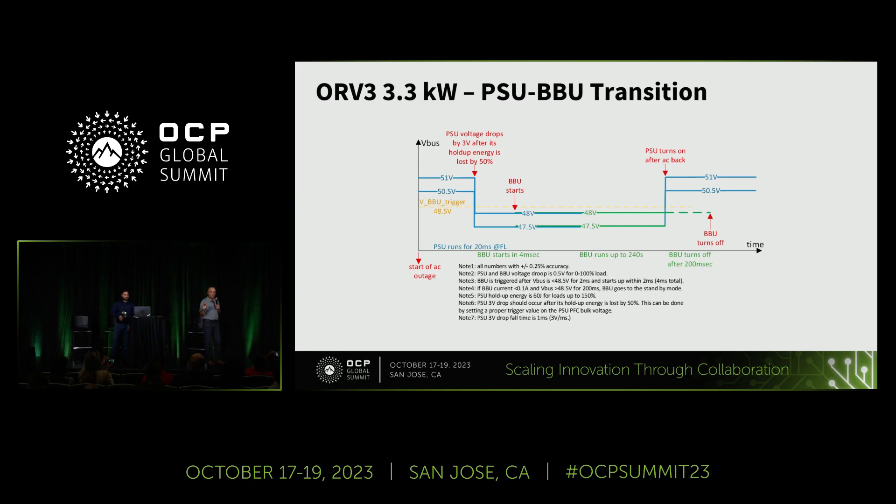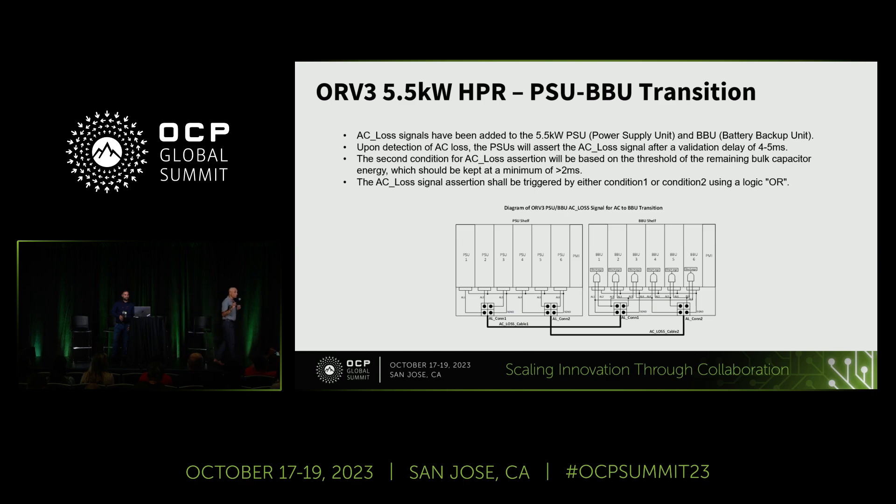These are the key differences as we move from the 3.3 kilowatt power shelf to the 5.5 kilowatt power shelf. The real key feature is the PSU to BBU transition. In the past, there was no signal — you drop straight three volts or when the holdup capacitor had depleted its energy by 50%. Now there are two criteria operated in an OR manner: a cable connection carrying the AC loss signal between the PSU and the BBU module, and a second condition where the capacitor energy has enough holdup for two milliseconds. Either condition triggers the transition.